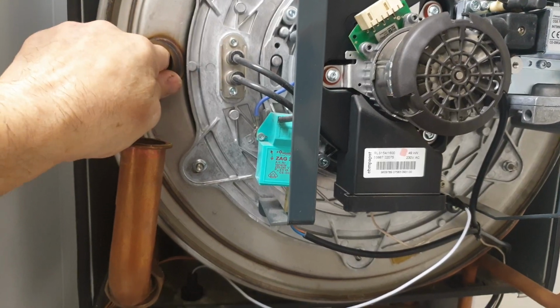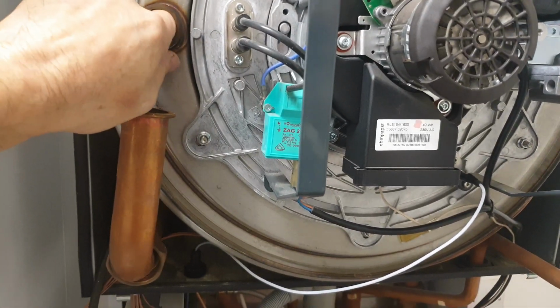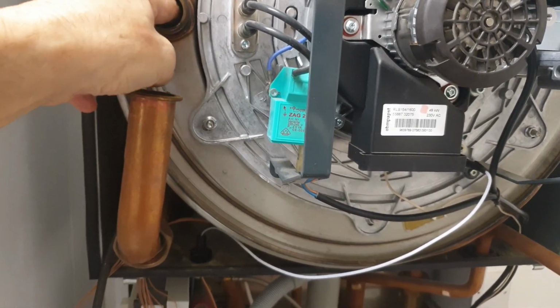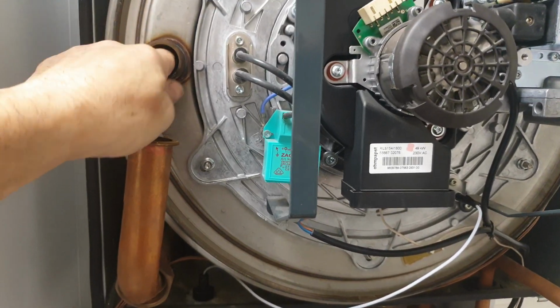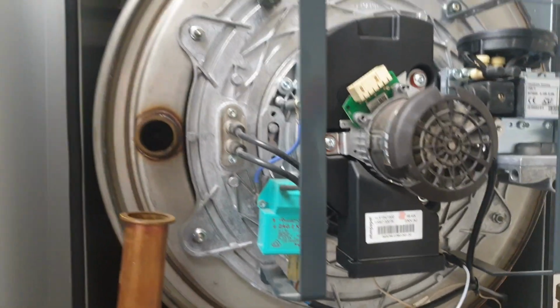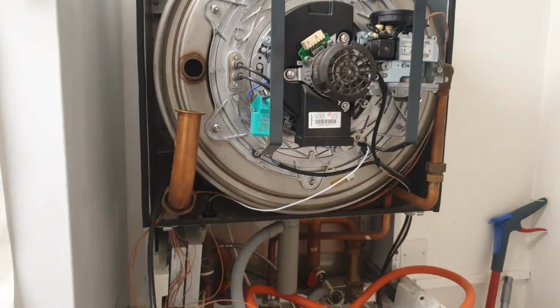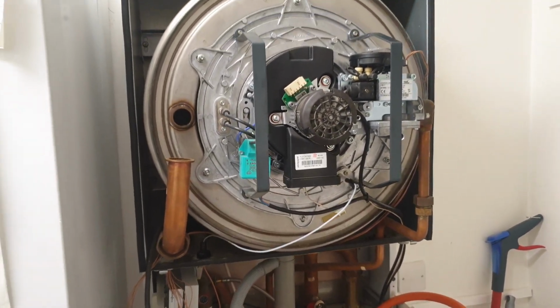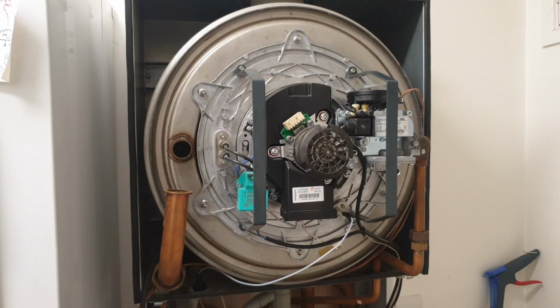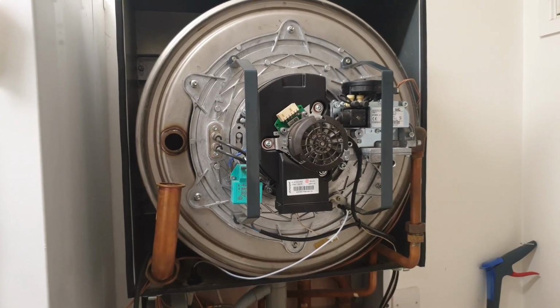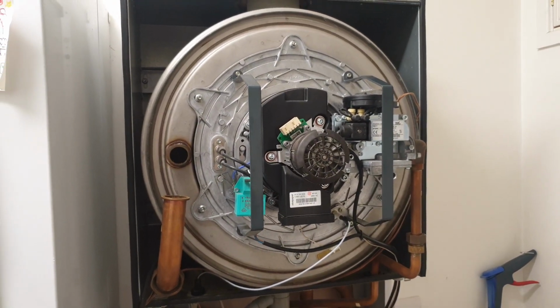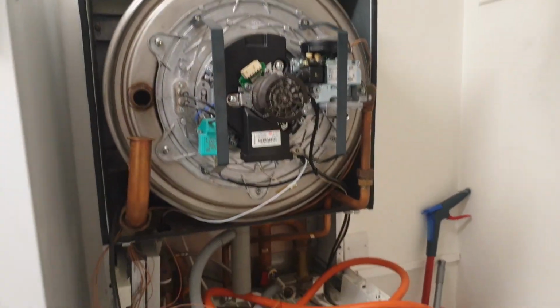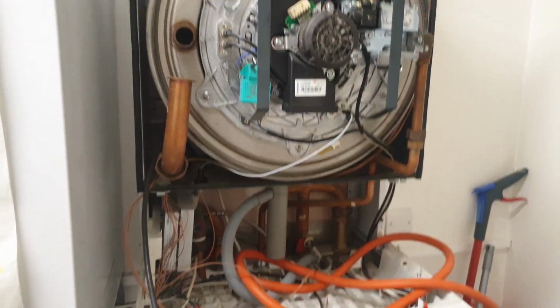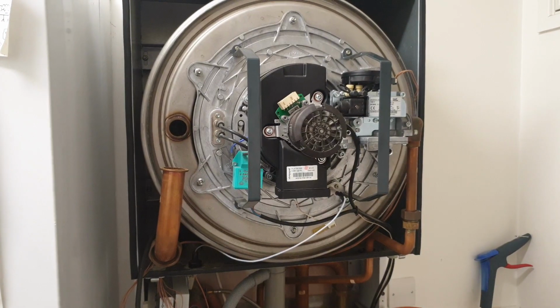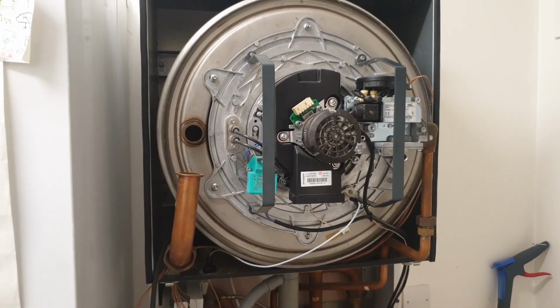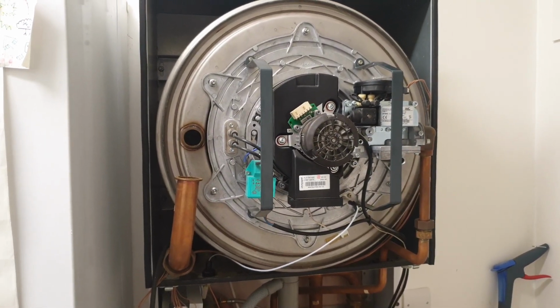I'm not advocating using aluminium heat exchangers just because they don't suffer this problem, and I am assuming they don't suffer the problem based on my own experience. But anyway, rubber hoses are not the cause of dirt and blockages in the boiler. Basically, if they're removed and serviced as part of the annual service, kept clean, like any other component of a boiler that might get dirty, you don't have an issue. I've got hoses on boilers now 15 years old with no issues and no need for renewal.